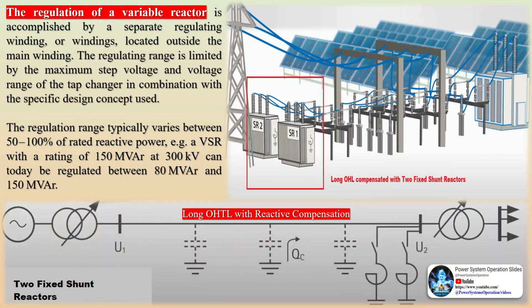The regulation of a variable reactor is accomplished by a separate regulating winding, or windings, located outside the main winding. The regulating range is limited by the maximum step voltage and voltage range of the tap changer in combination with the specific design concept used. The regulation range typically varies between 50 to 100% of rated reactive power.